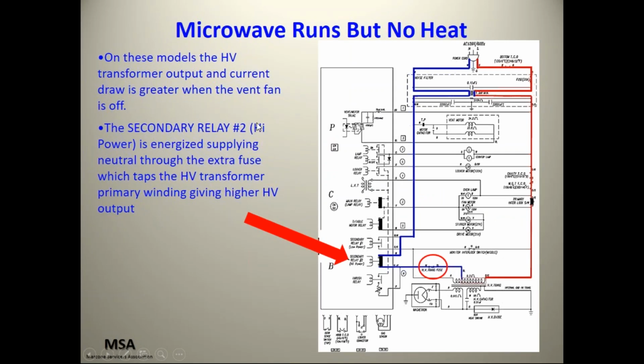The secondary relay, this is what's feeding that fuse for high power. Okay. The secondary relay, high power, is energized, supplying neutral through the extra fuse, which taps the high voltage transformer primary winding, giving higher high voltage output.